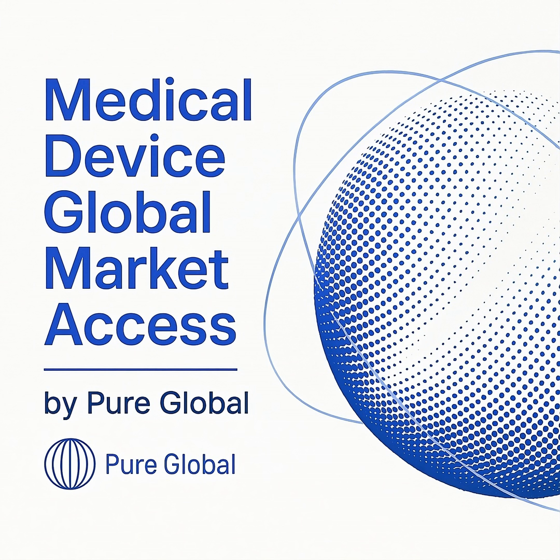The initial importer, however, carries a much heavier regulatory burden. According to FDA Regulation 21 CFR Part 807.3(g), the initial importer is the entity that furthers the marketing of a device from a foreign manufacturer to the final seller. This is not just a logistical role, it is a key compliance function. The initial importer is responsible for the device's regulatory adherence once it enters the U.S. This includes ensuring the device has the appropriate marketing authorization, such as a 510(k) clearance, de novo classification, or pre-market approval, PMA. Furthermore, the initial importer has significant post-market responsibilities.